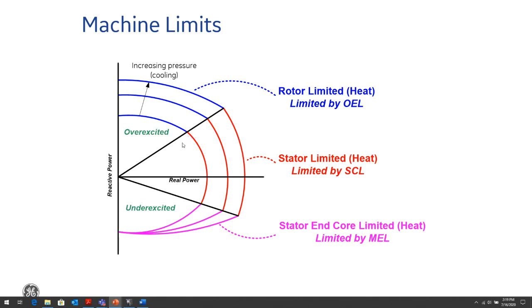So what we really need to be operating in is this red part of the curve for the normal operation of the generator. Once we start getting outside the red part of the curve, we go into the blue: the overexcited portion of the curve, which we refer to as the OEL, or the overexcitation limit of the generator, or the underexcited part of the curve, which we usually refer to as the MEL, or the minimum excitation limit of the generator or machine. When we're in the underexcited part of the curve, the machine becomes inductive. It becomes like an induction motor, so that it starts to draw high reactive current, which overloads the stator, induces currents in the rotor, and causes overheating in the machine and, over time, damage to the machine.